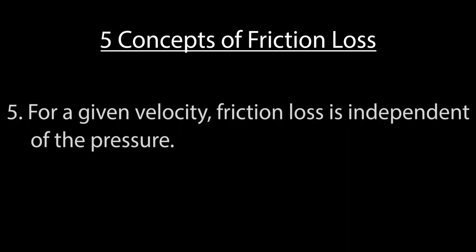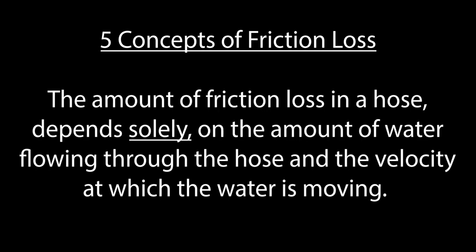for a given velocity, friction loss is independent of the pressure. The amount of friction loss in a hose depends solely on the amount of water flowing through the hose and the velocity at which the water is moving.